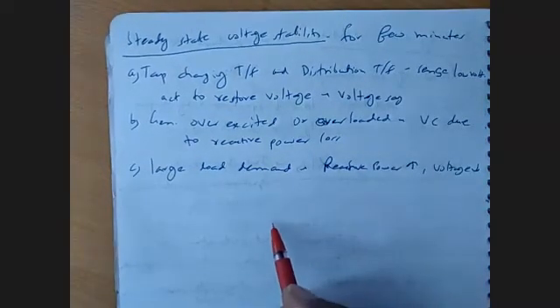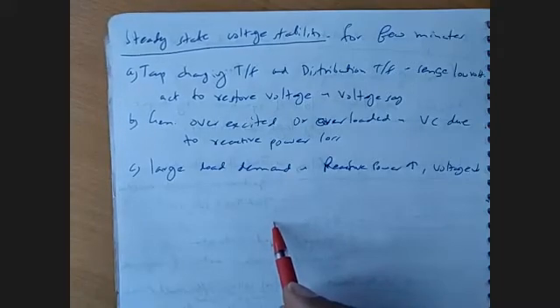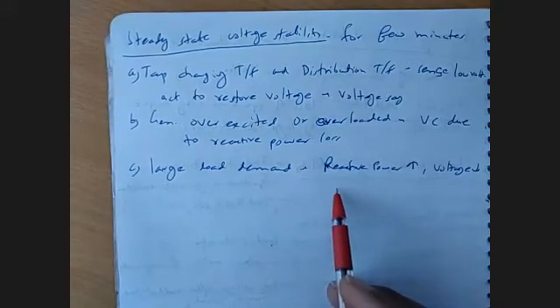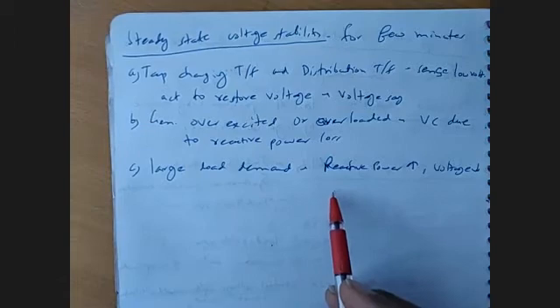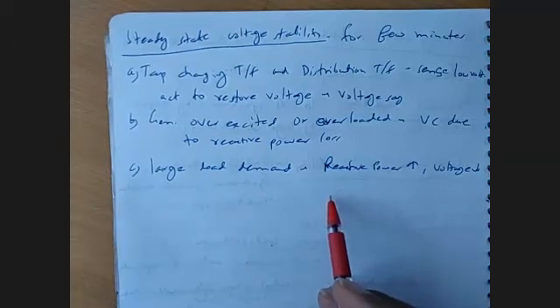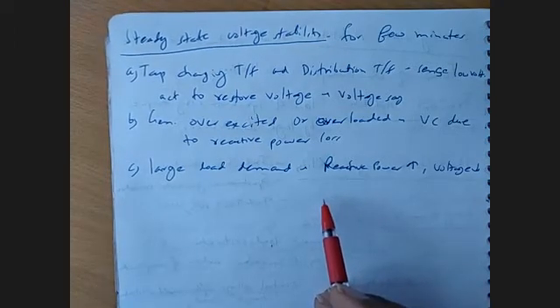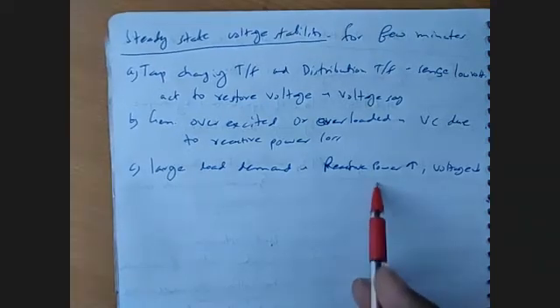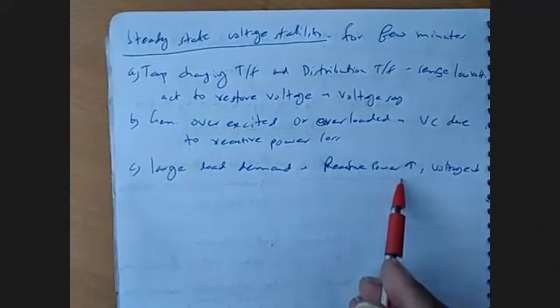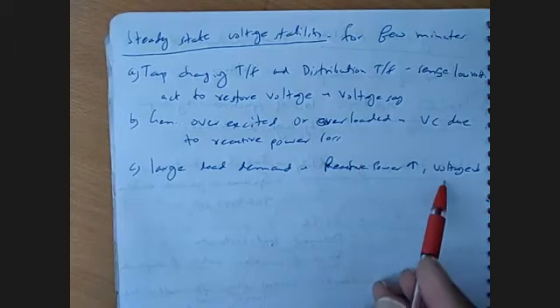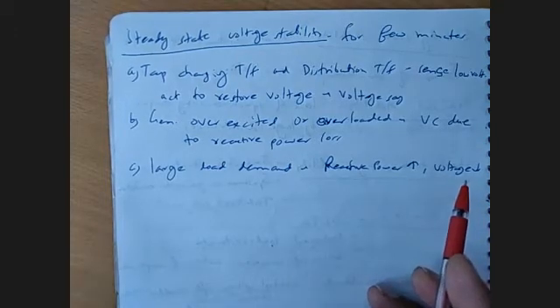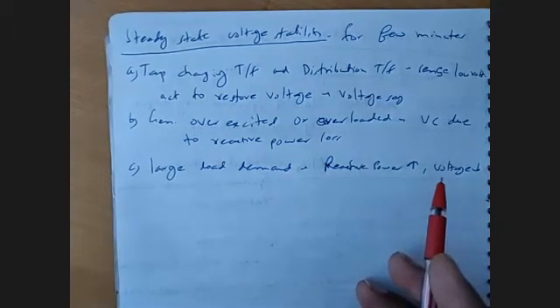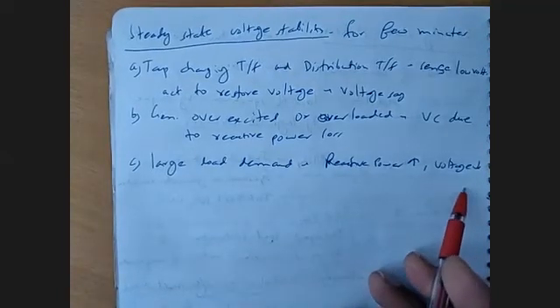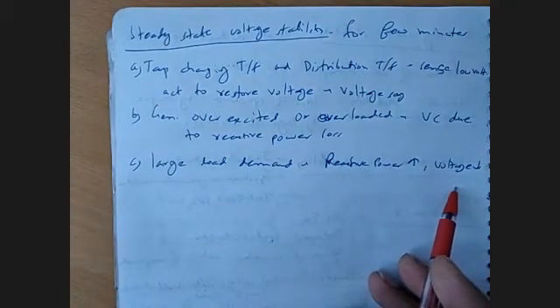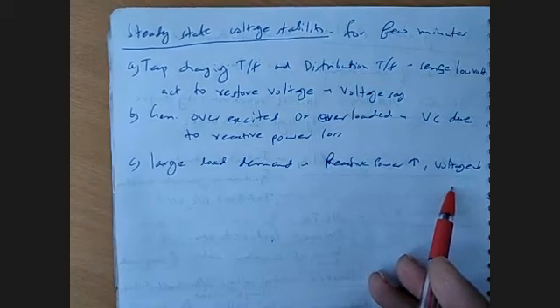Due to the large load demand or large rapid magnitude of the power transfer, reactive power demand will increase, and due to this increase in the reactive power demand, voltage will reduce in the system. So this is the basic cause for steady state voltage stability in the system.